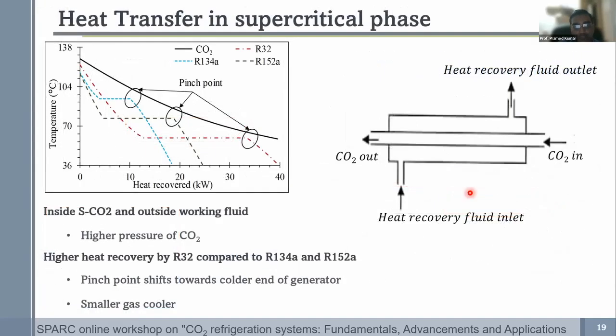So in terms of the heat transport properties, as Professor Maiya also mentioned, in a conventional subcritical cycle you are hit by these flat lines inside the two-phase region. But in a supercritical regime, when heat transfer takes place above the critical point, this is the kind of heat transfer characteristic. So you have to be very careful when you select another working fluid that undergoes phase change and is exchanging heat with carbon dioxide. These are some of the things that you need to look at in the engineering aspect when you build or develop a heat exchanger for a transcritical system.